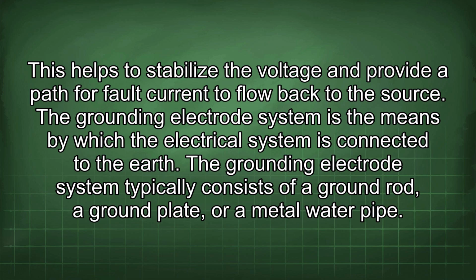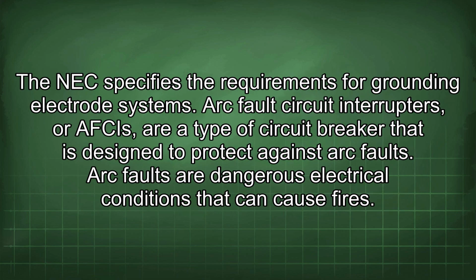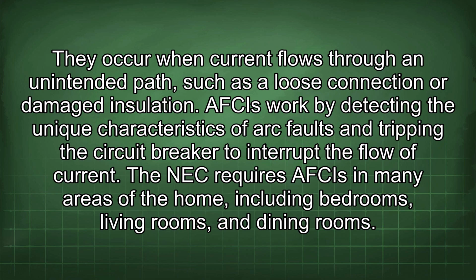The grounding electrode system is the means by which the electrical system is connected to the earth. The grounding electrode system typically consists of a ground rod, a ground plate, or a metal water pipe. The NEC specifies the requirements for grounding electrode systems. Arc fault circuit interrupters, or AFCIs, are a type of circuit breaker that is designed to protect against arc faults. Arc faults are dangerous electrical conditions that can cause fires. They occur when current flows through an unintended path, such as a loose connection or damaged insulation. AFCIs work by detecting the unique characteristics of arc faults and tripping the circuit breaker to interrupt the flow of current. The NEC requires AFCIs in many areas of the home, including bedrooms, living rooms, and dining rooms.